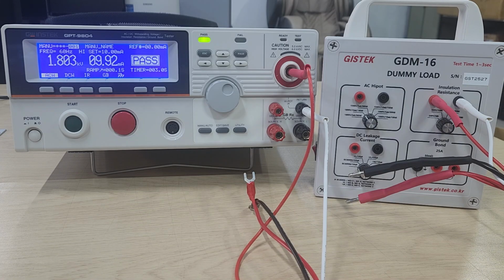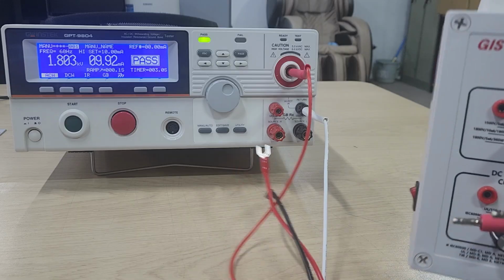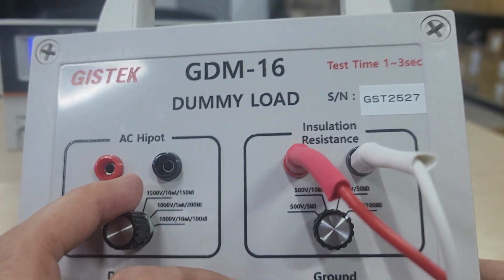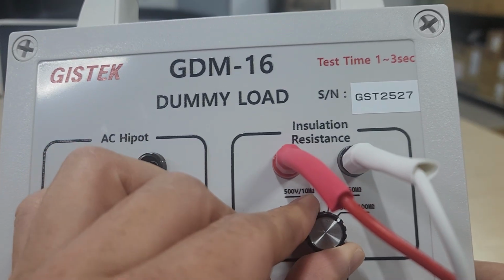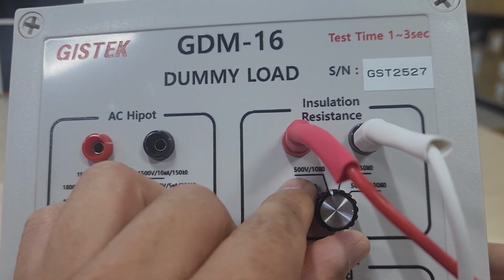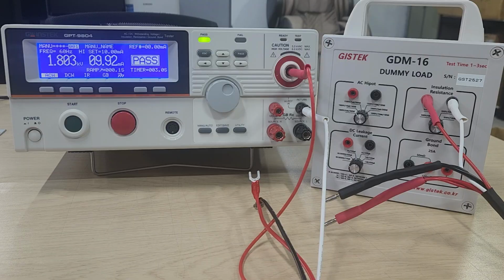Select the DC insulation resistance test channel from the dummy load. For example, turn the knob to set the 500 volt and 10 megaohm channel. Next, set the test condition of the DC insulation resistance tester to 500 volts, 10 megaohms, 3 seconds, the same as the condition selected for the dummy load.